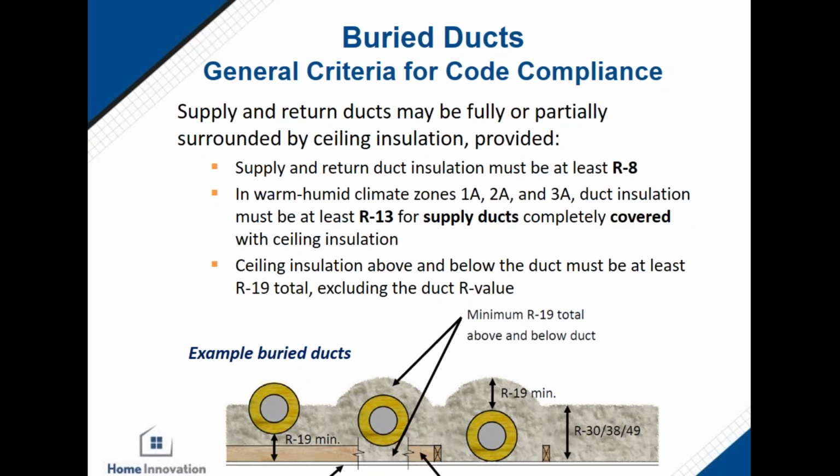So certainly, if they're installed properly, I think you have potential condensation for any flex duct or any duct installed in an attic. I think that concentric flex duct option or method maybe is not the most practical. It's just a way. We've done it. It's a way to get at least R13 duct insulation.